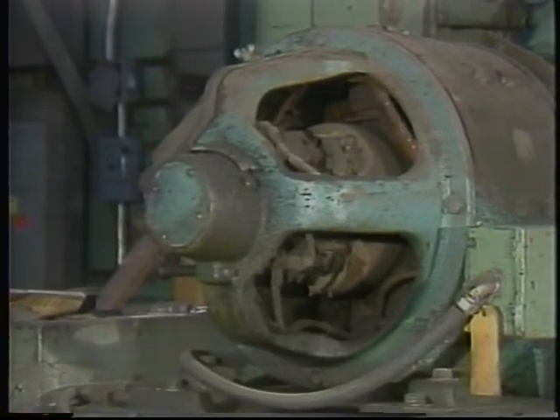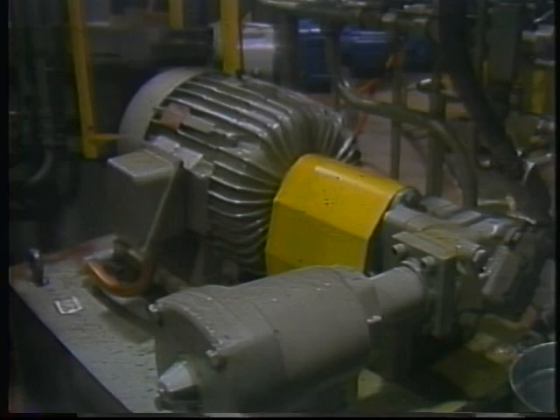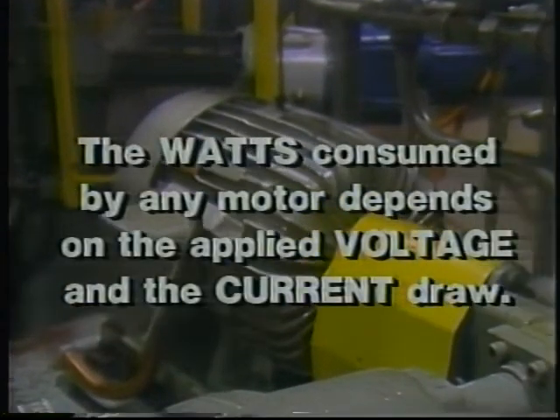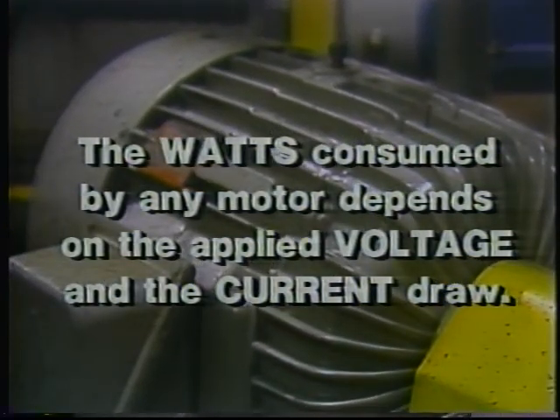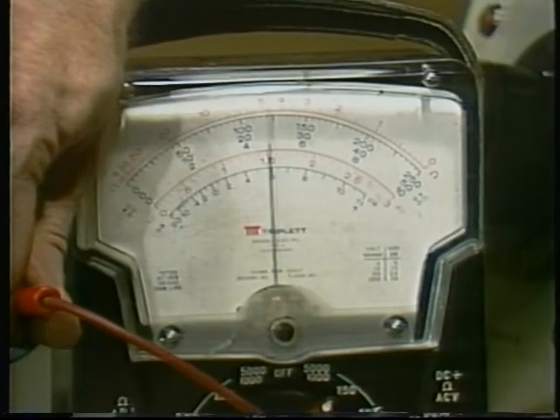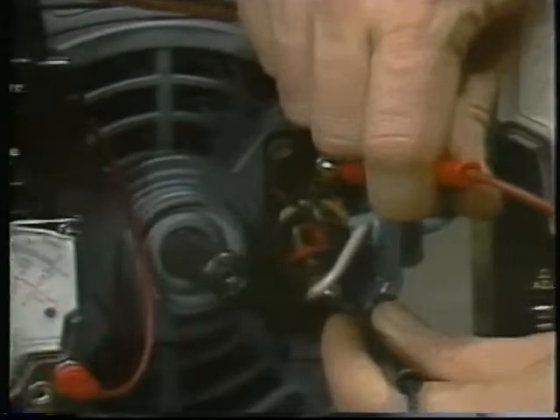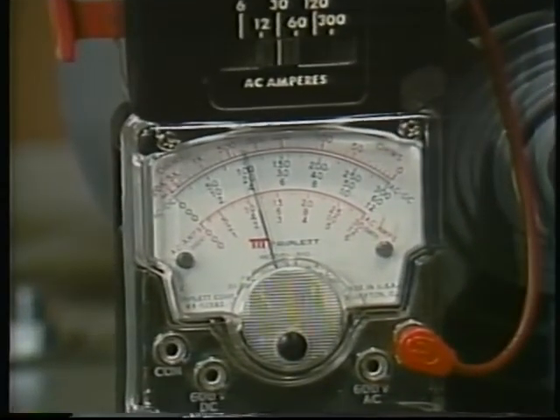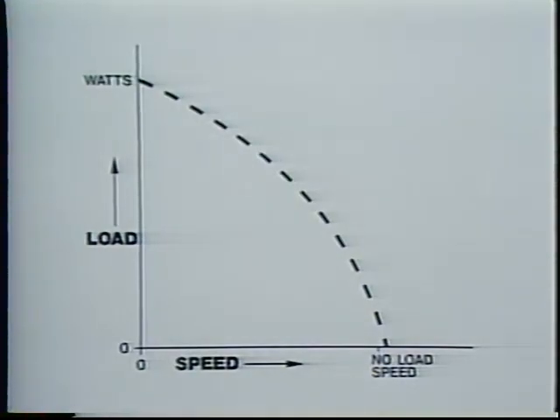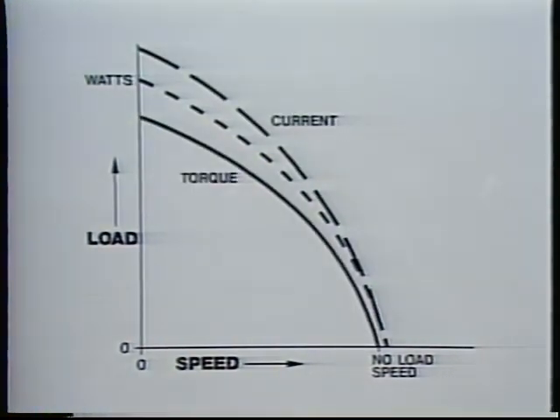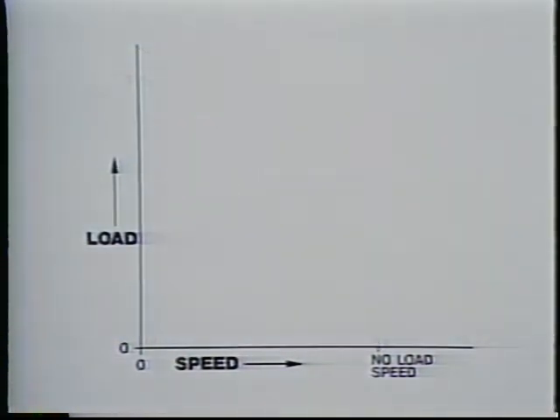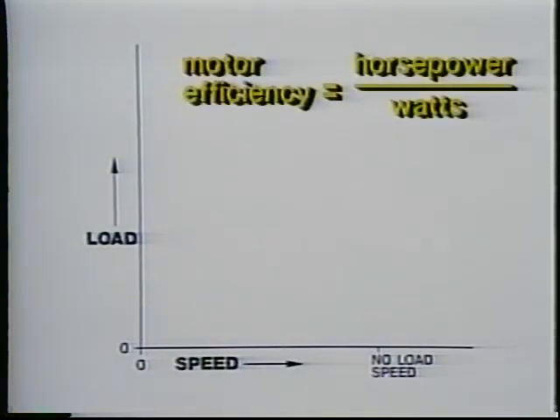When the power is AC, the relationship is a little more complicated, but the watts consumed by a motor always depend directly on the voltage applied and the current it draws from the line. Most motors operate at a fixed line voltage, which means that the watts into a motor depend largely on the current. If we plot watts of power consumed against motor speed, the curve looks like the current curve — or the torque curve — since the torque a motor exerts to drive its load depends on the current.